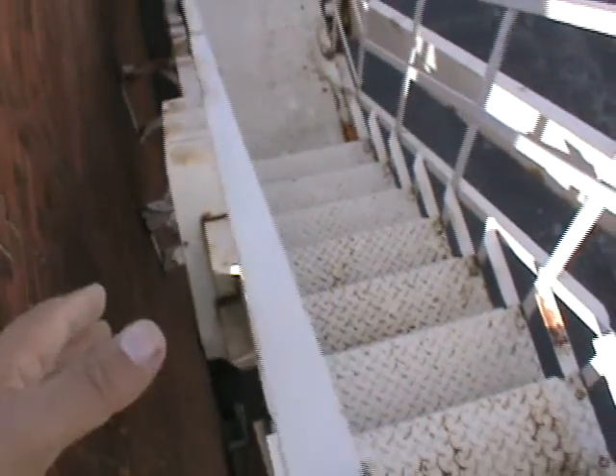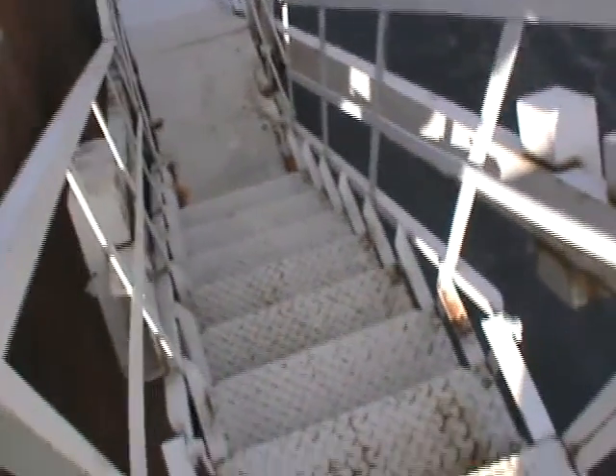All right, this fire escape was hit by a truck, cantilevered unit. This is way whacked over. This is whacked over now right here, and it's up against the cantilever. It's non-functional. It doesn't operate correctly, so this is a life safety issue. And I've put orange coloring. So again, original hardware.